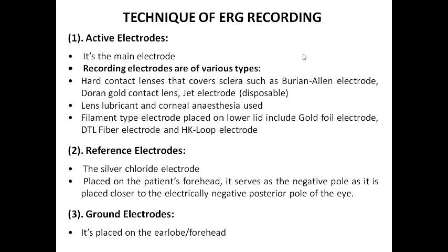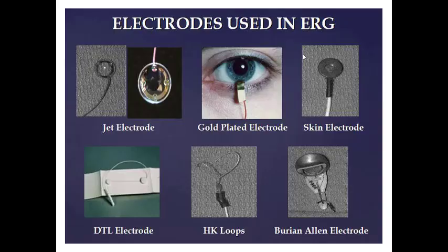The second type are reference electrodes, made up of silver chloride, placed on the patient's forehead, serving as a negative pole as it is placed closer to the electrically negative posterior pole of the eye. The third type is the ground electrode, placed on either the earlobe or forehead.